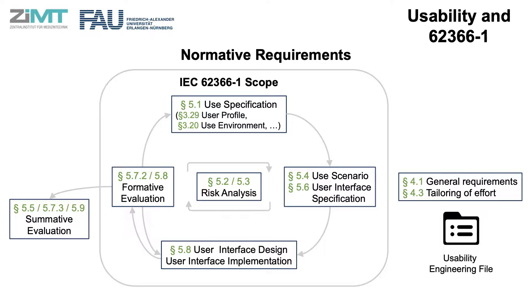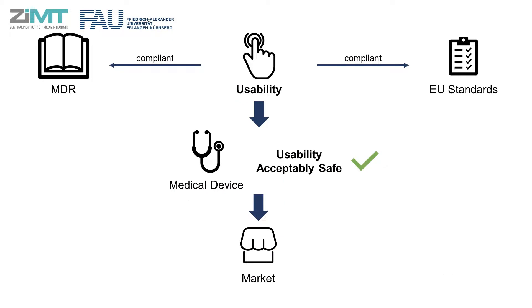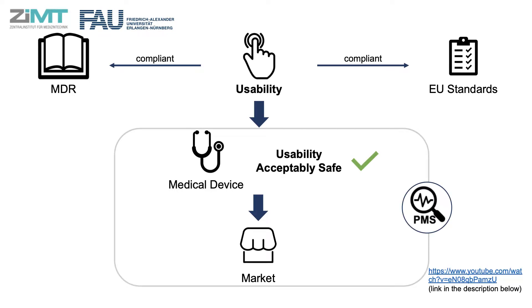Common methods used to perform the formative and summative evaluation are well described in Part 2 of the IEC 62366 standard. After these steps, if the device can be defined as acceptably safe from the point of view of usability, it can then be placed on the market. The identification of risks associated with use does not end there, however, as it is part of the life-cycle process of a medical device. The monitoring of these risks is achieved through after-sales surveillance processes, also called post-market surveillance, or PMS for short.